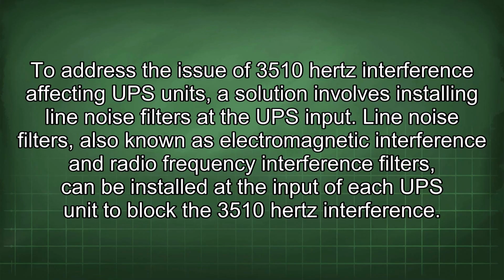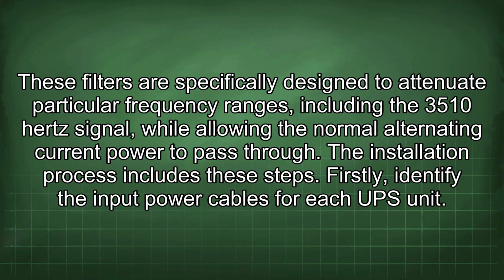To address the issue of 3,510 Hz interference affecting UPS units, a solution involves installing line noise filters at the UPS input. Line noise filters, also known as electromagnetic interference and radio frequency interference filters, can be installed at the input of each UPS unit to block the 3,510 Hz interference. These filters are specifically designed to attenuate particular frequency ranges, including the 3,510 Hz signal, while allowing the normal alternating current power to pass through.